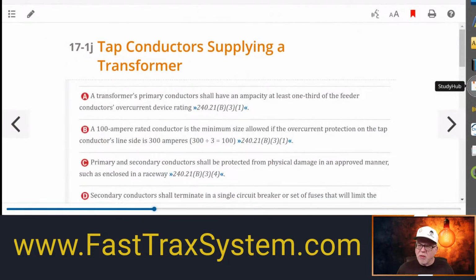Okay, so what about taps that are supplying a transformer? So this is another one, because the conductor sizing we just did is pretty straightforward if you realize those type of things. And we'll get deeper in future episodes where I break down how the continuous and non-continuous loads on the secondary impact the primary and how you would break those things down. But again, if you follow the conductor rules, as we just said, you're typically not going to have any problem at all anyway.